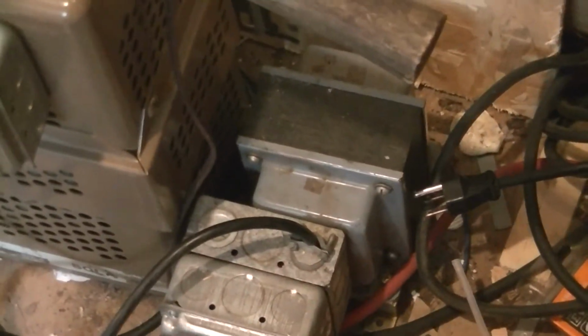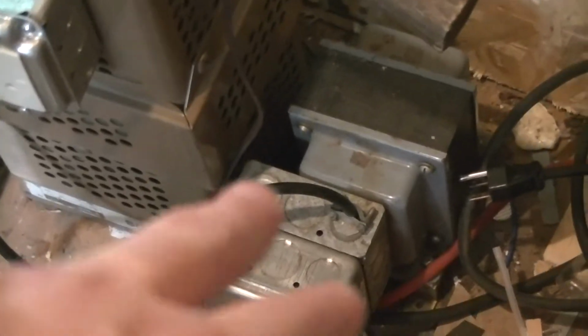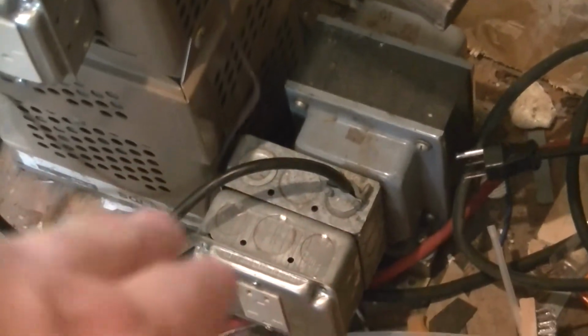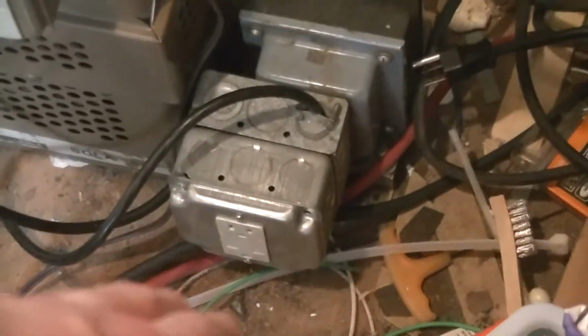What that means is that the transformer, in this case both its primary and its secondary, have a pair of 120 volt windings, and whether the winding is for 120 volts or 240 volts is dictated by whether the windings are wired in parallel or in series. In this case, the primary windings are configured for 240 volts, and the secondary is configured for 120 volts.